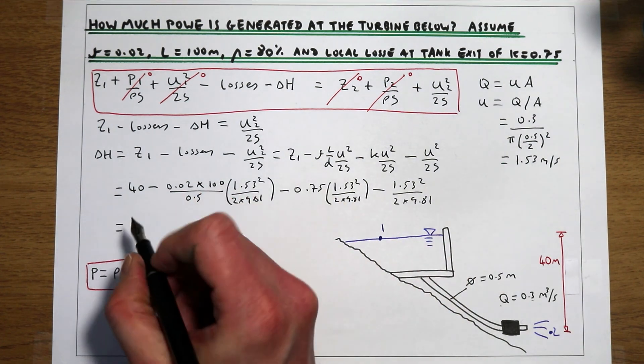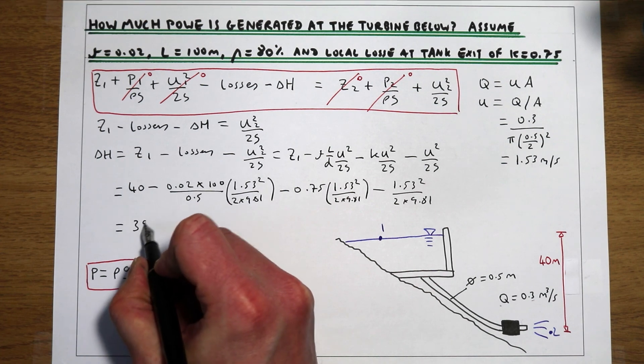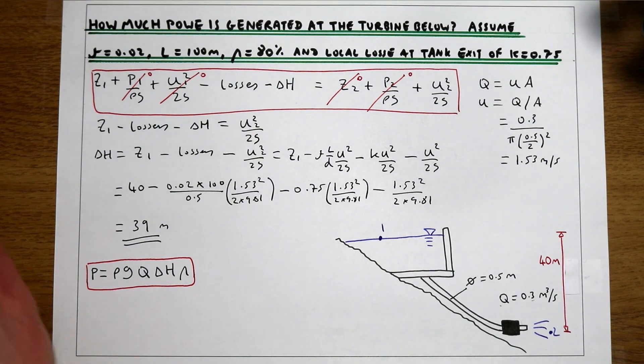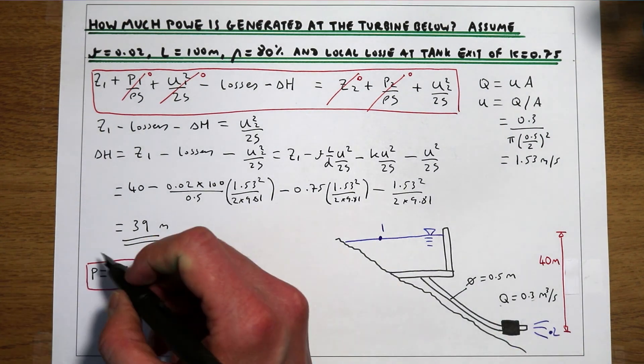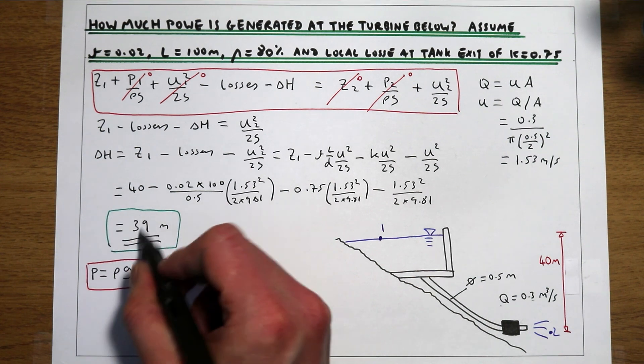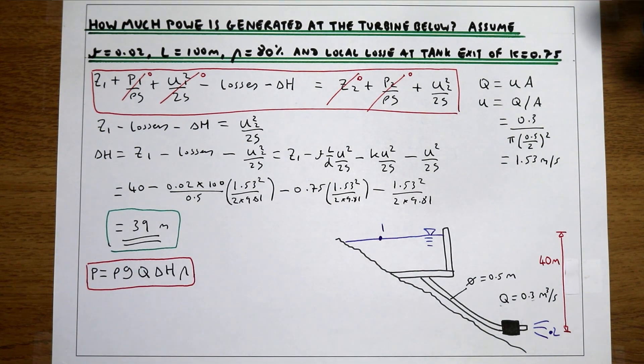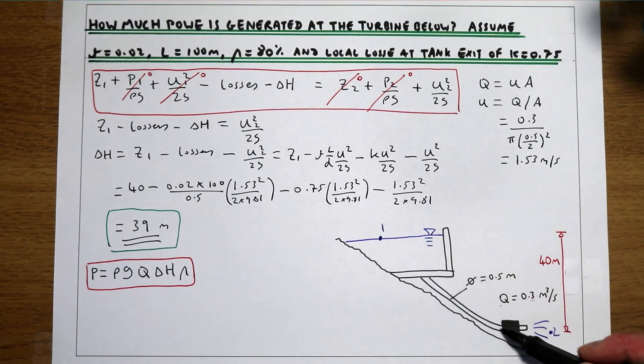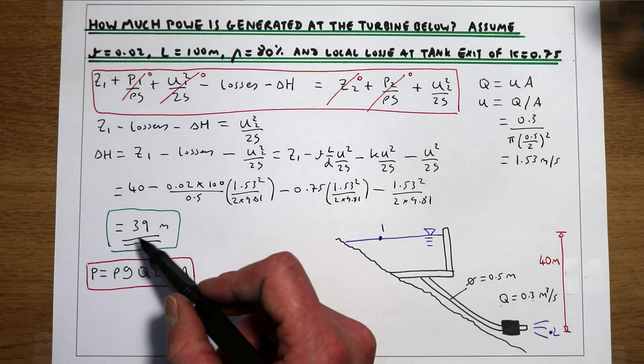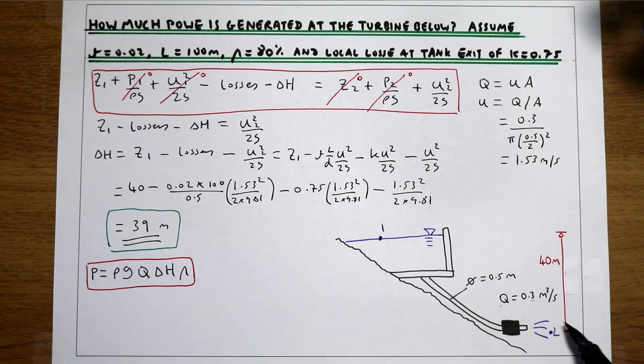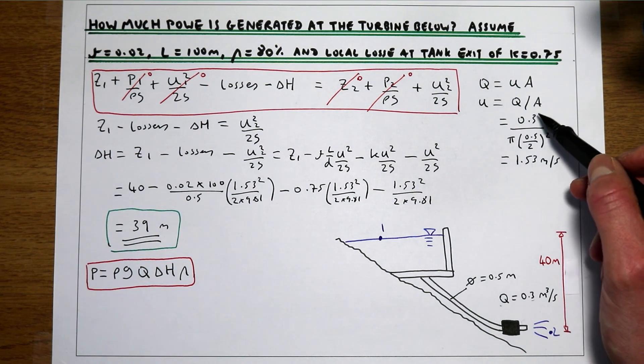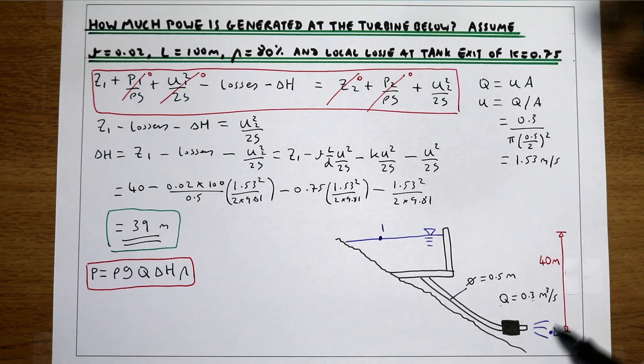Once we've plugged the numbers into that equation, we end up with a delta H of 39 metres. What that answer is telling us is that the turbine is extracting 39 metres of pressure head from the flow. We start out with energy at point 1, have losses in the pipe, the turbine extracts 39 metres of energy from the flow, and we're left with a velocity of 1.53 metres per second and a flow of 0.3 metres cubed per second coming out of the pipe.